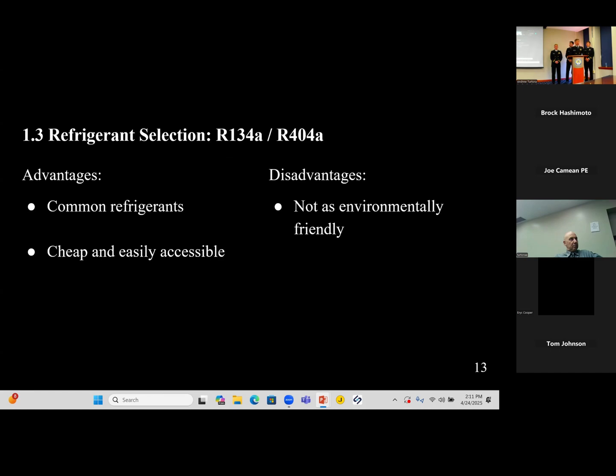First thing we're going to look at is R134A and R404A. These are two of the most common types of refrigerants, so they are easily accessible in most parts of the globe, and they are relatively cheap compared to other refrigerants on this list. Now, the disadvantage to these, especially with R134A, is it has a high global warming potential. And for that reason, there's a likelihood of it being phased out in the near future. So we decided not to go with this refrigerant for that reason.